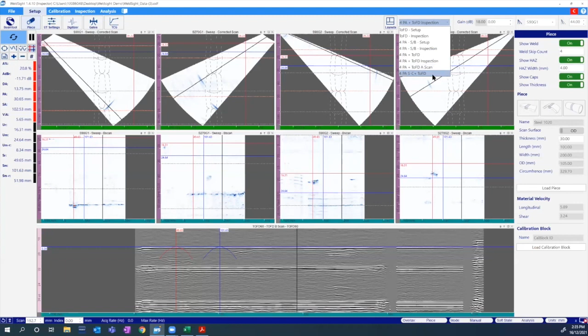So one more important feature what we have is the merging function. As we move on to the phased array, we can merge all our phased array scans together. And we can also re-import the configurations. Let's say you have defined this as a plate, but during analysis, you have the option to redefine it as a pipe by simply loading the piece directly from your beam tool.